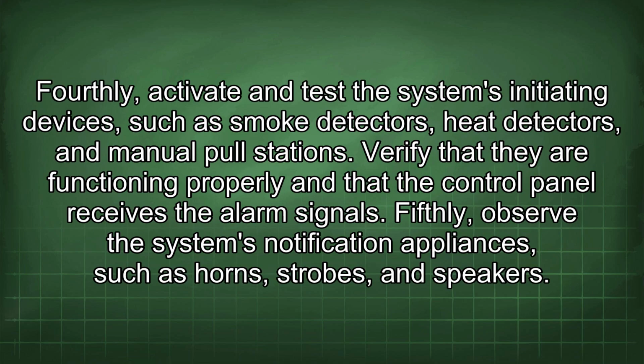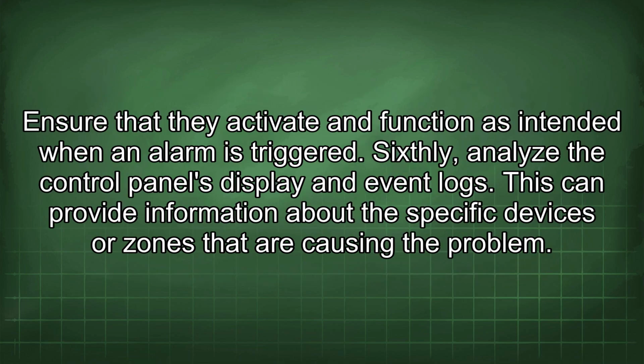Fourthly, activate and test the system's initiating devices, such as smoke detectors, heat detectors, and manual pull stations. Verify that they are functioning properly and that the control panel receives the alarm signals. Fifthly, observe the system's notification appliances, such as horns, strobes, and speakers. Ensure that they activate and function as intended when an alarm is triggered.